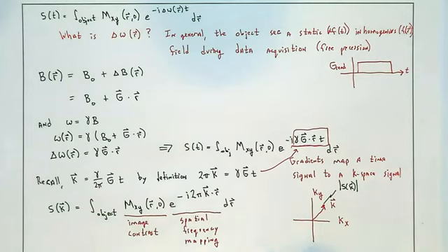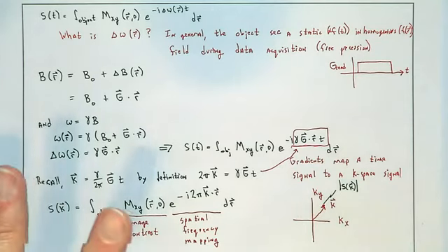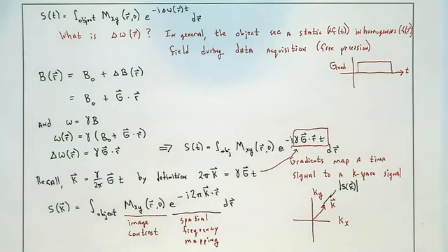And I want you to remember that a point in k-space is getting information from the whole slice, because our coils are just listening to whatever you excited. Generally, you excited the whole slice. So you're getting all of that information, but you're filtering out a specific part of the information from the slice. And that filtering comes from the application of a specific spatial frequency. This lets you sample just one spatial frequency for a very brief period of time before moving on to its neighbor and its neighbor. Filling in all of the k points to fill k-space ultimately gives us an estimate of the magnitude of all of these spatial frequencies. And that in turn, through the 2D Fourier transform, recovers an image of the underlying object.